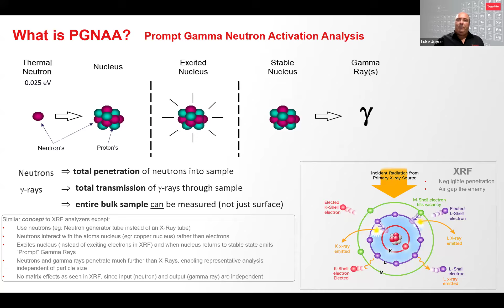Since PGNAA can penetrate the entire sample and is independent of particle size, it can measure the entire material flow on conveyor belts, not just the surface, and can measure large volumes, tens of litres, of slurry independent of particle size distribution. Other technologies such as XRF, XRD, and other spectral or laser techniques have very limited penetration, which prevents online analysis of coarse particles and lighter elements, typically below calcium.